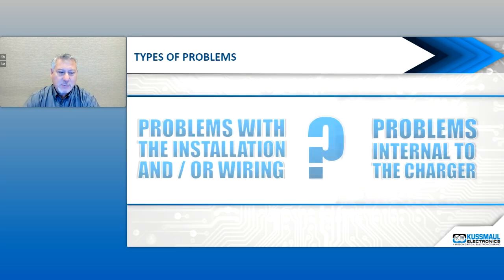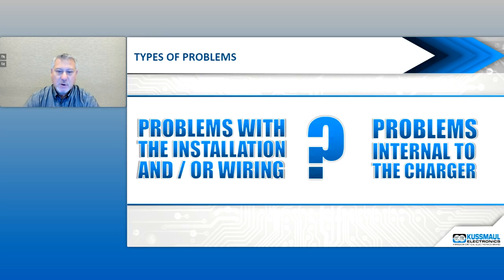So, common problems we come across: some of the easiest ones involve the alternating current shorelines coming in. We regularly see issues where fire stations have a cord reel attached to the ceiling, and it looks like the plug is plugged in, but over time it's worked loose and isn't actually connected.